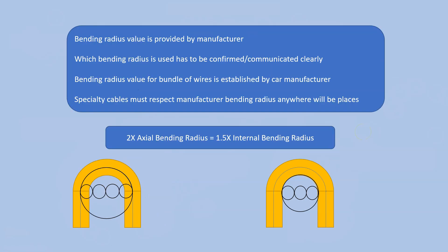This is the main answer: the bending radius value is provided by the manufacturer. It can only come from the cable manufacturer — not the supplier, vendor, or salesperson — because they know what materials they used, what the cable is designed for, and they have conducted all the tests. They will have a datasheet stating the minimum bending radius. The bending radius of a cable cannot be calculated by you — you need to find it from the manufacturer.